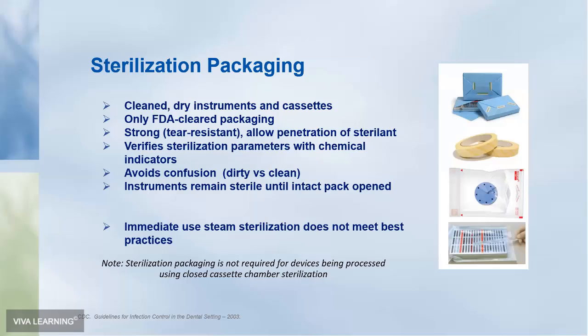The next stage is inspection. So you would inspect the instruments to make sure they're not damaged and they're free of any debris and soil. After that, you would move to sterilization packaging. Again, they have to be clean, and the instruments and cassettes, if you're using cassettes, also have to be dry. The sterilization packaging is FDA cleared. It needs to be strong and tear resistant, and it has to allow penetration of the sterilant. If it's been FDA cleared as packaging, it's been tested for penetration, and there is data that's provided on penetration of the sterilant and the strength.